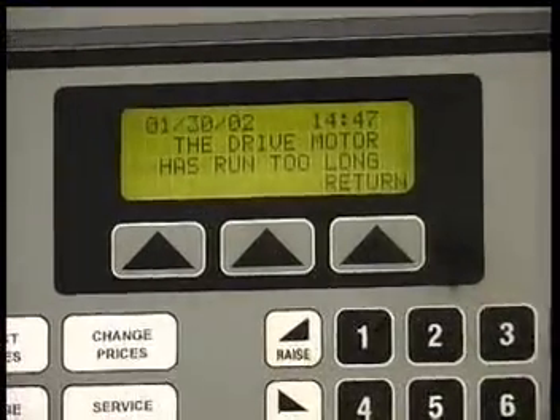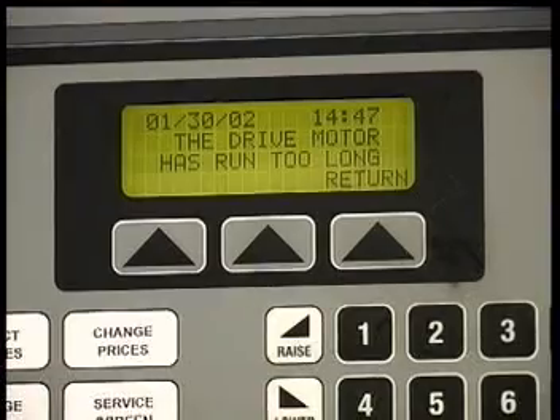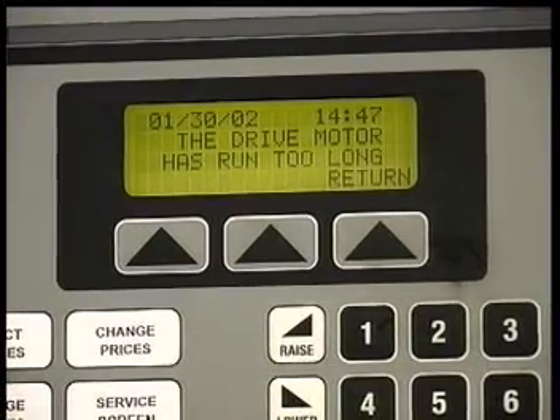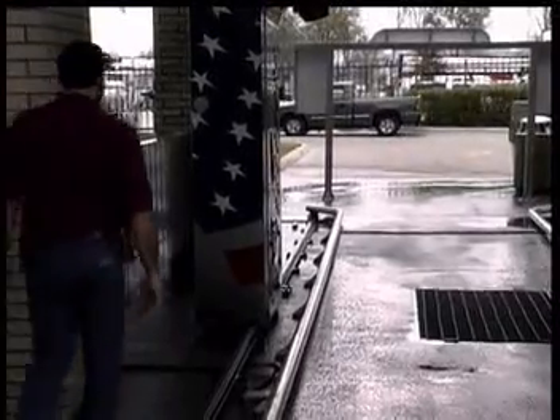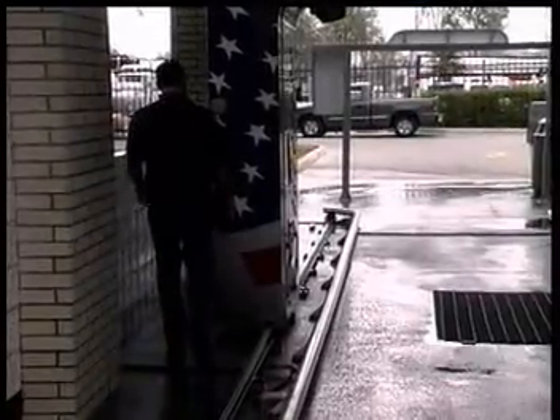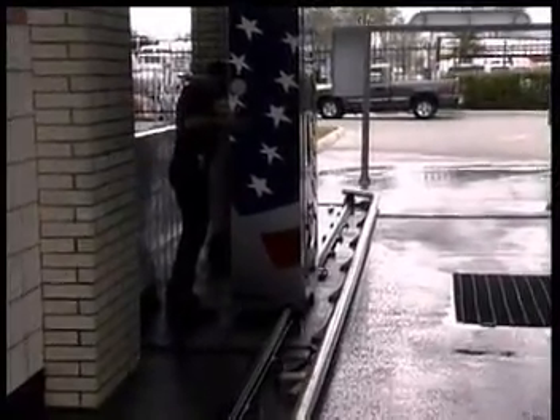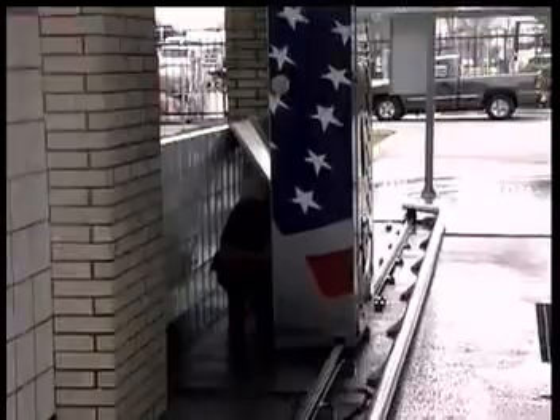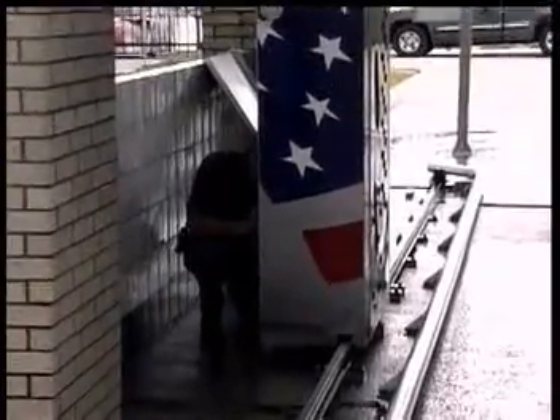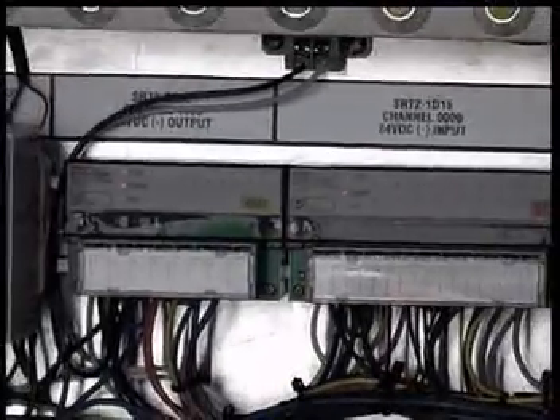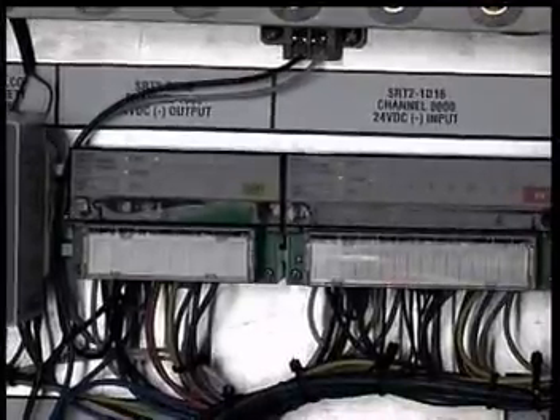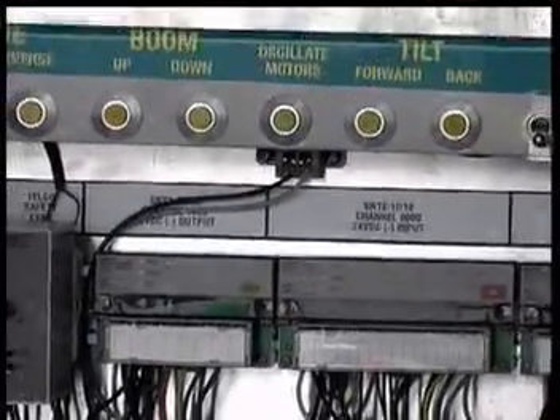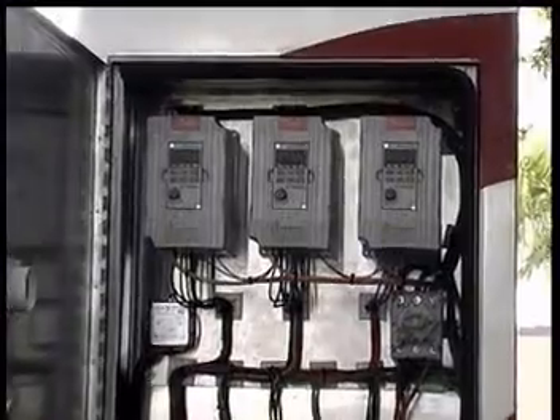If the drive motor runs more than 2 minutes, this fault will display and the processor will disable the entrance controller. When troubleshooting, first determine the location of the wash gantry. If the gantry is in the middle of the track, check for a physical blockage and that the track is straight. Then check for a loss of power supply to the gantry. Check for power lights on the input-output cards and the Danfoss motor drives.